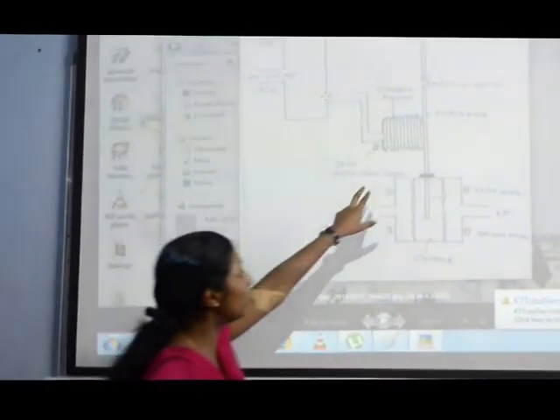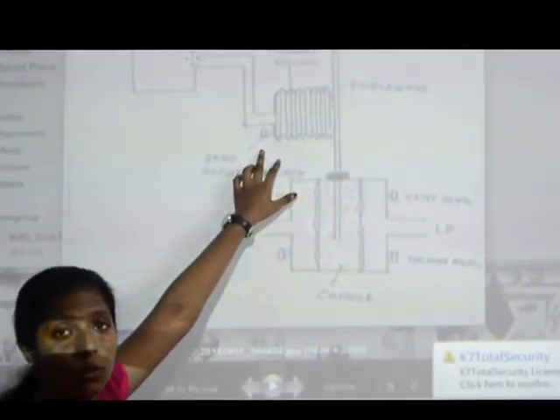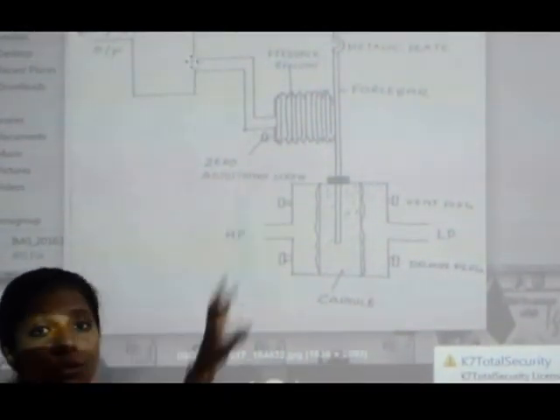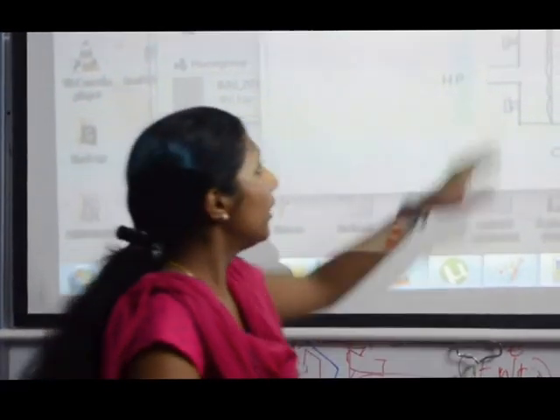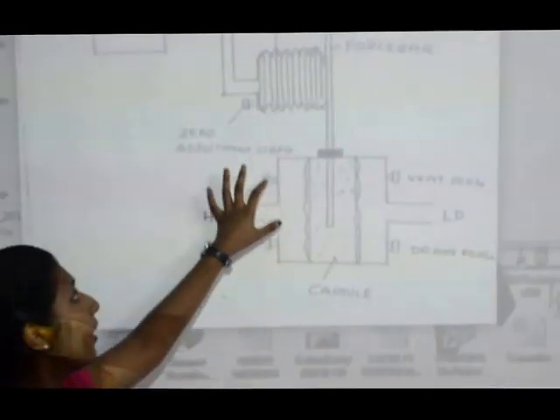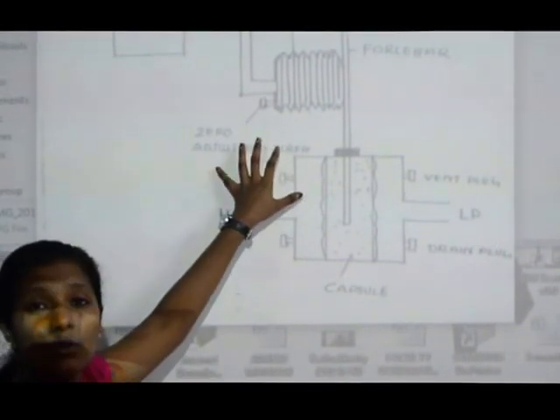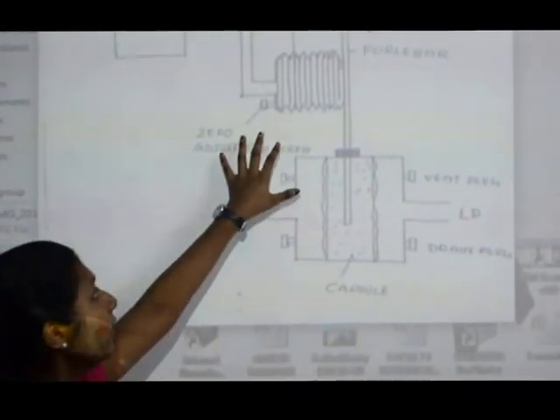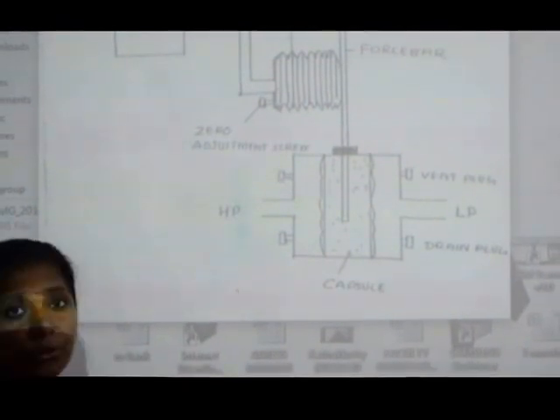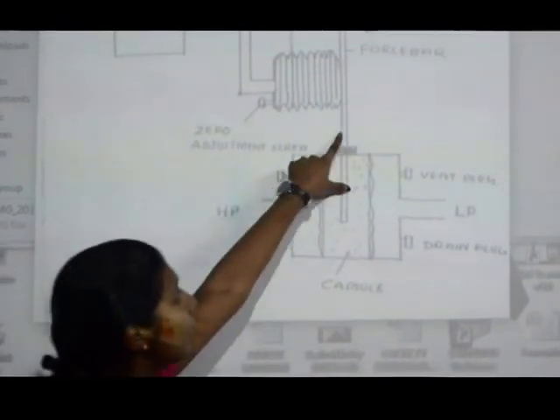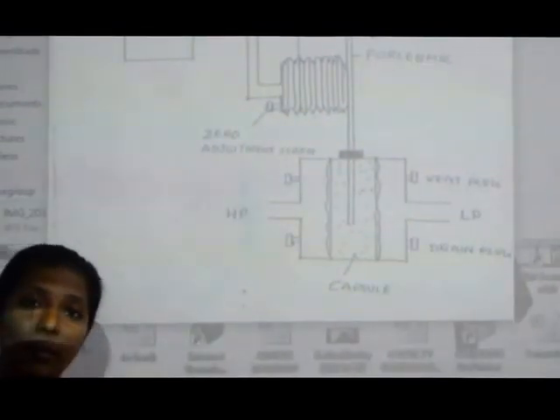Here we are able to see a feedback bellows. In this bellows, we are having a screw. Here only we are able to do zero calibration. Connected to this feedback bellows, we are having a zero adjusting screw. Here only we are doing our zero calibration. If you want to do span calibration, we need to adjust this force bar. This is what is actually happening inside a pneumatic transmitter.